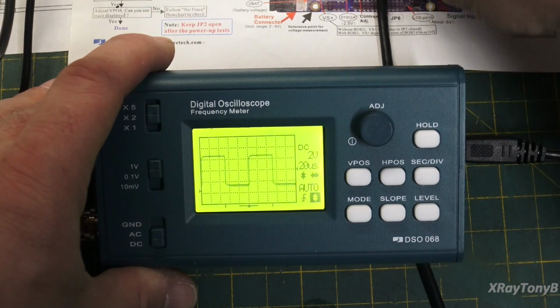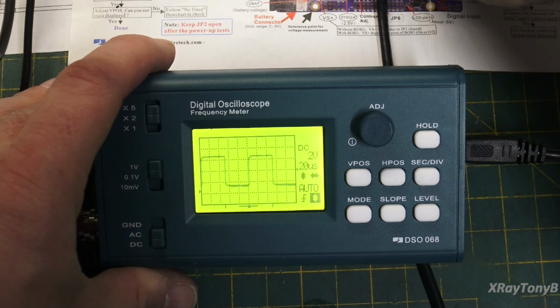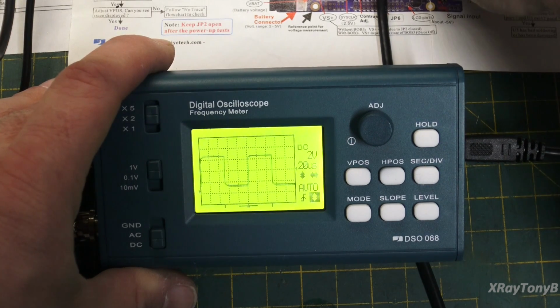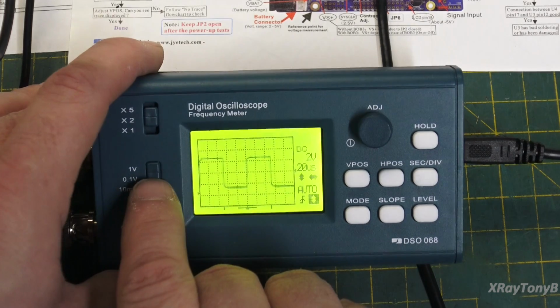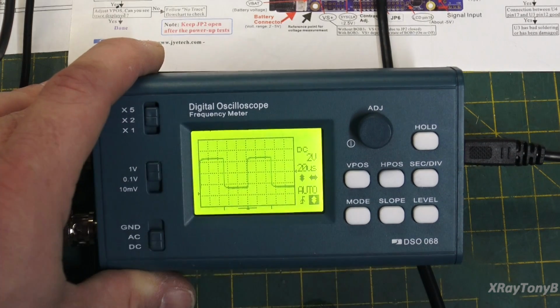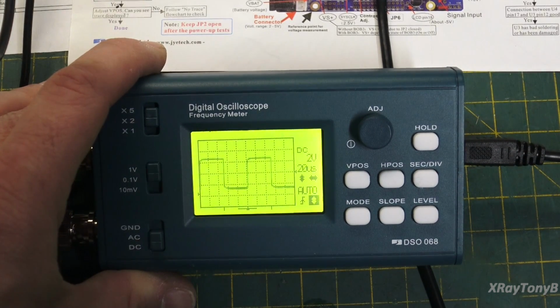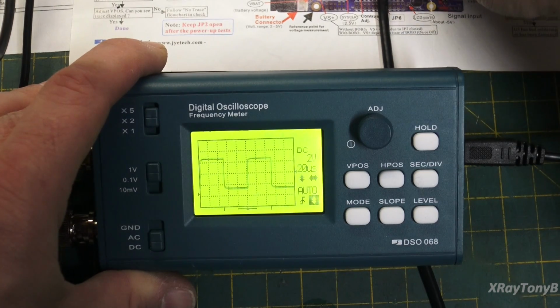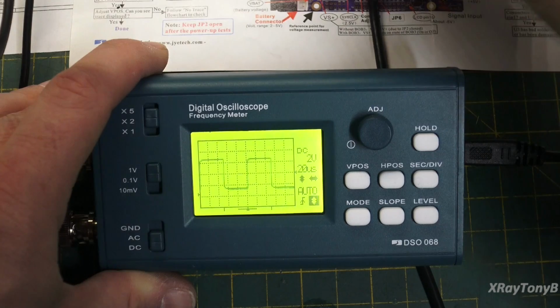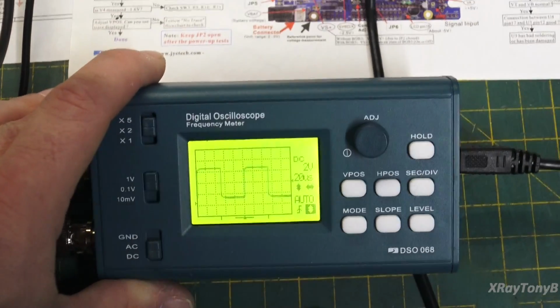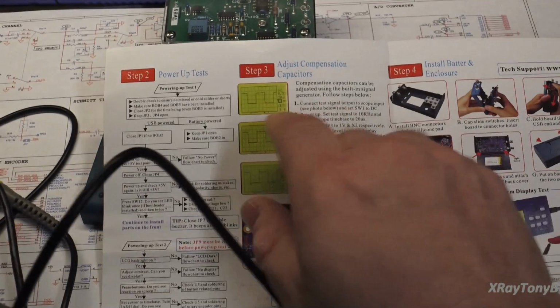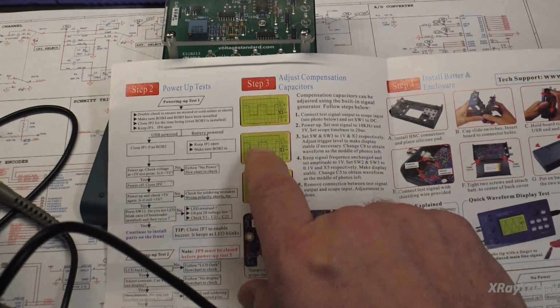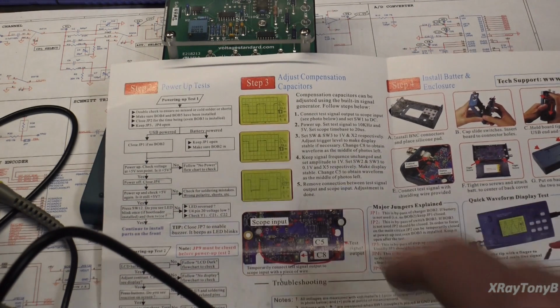Now, we want to set switch 2 and switch 3 to 1 volt and times 2 respectively. So we're at 1 volt and times 2. So that's all set. Adjust the trigger level to make the display stable if necessary. Change C8 to obtain the waveform as in the middle of the photos on the left. As you can see, it starts out as a curvy waveform, and they want you to adjust C8 until it's nice and square.